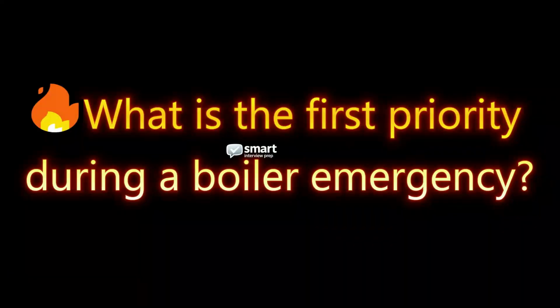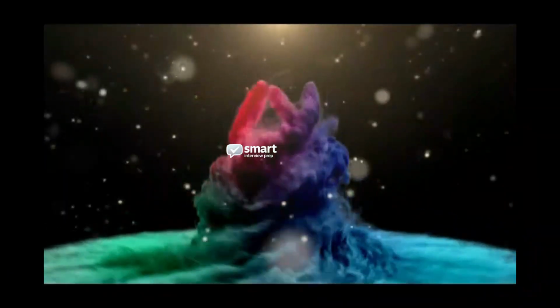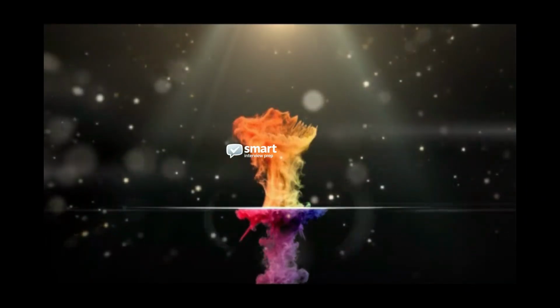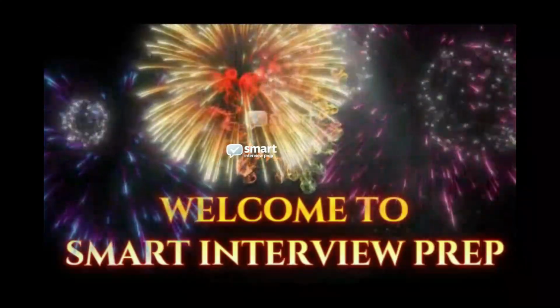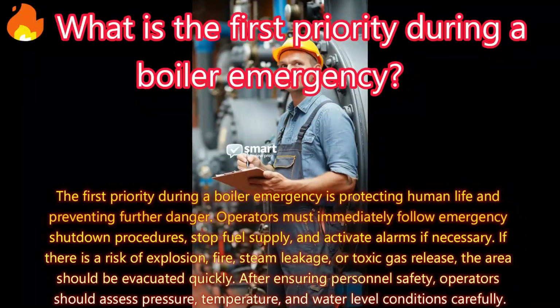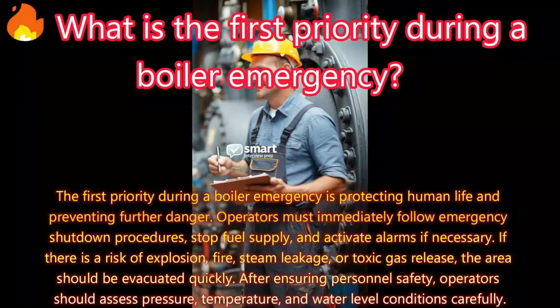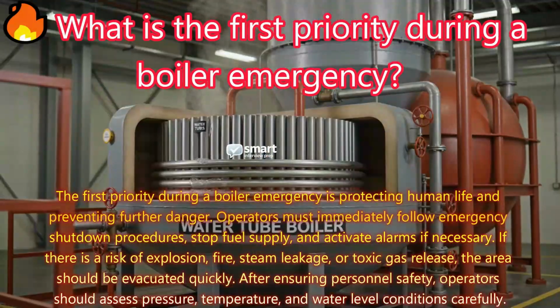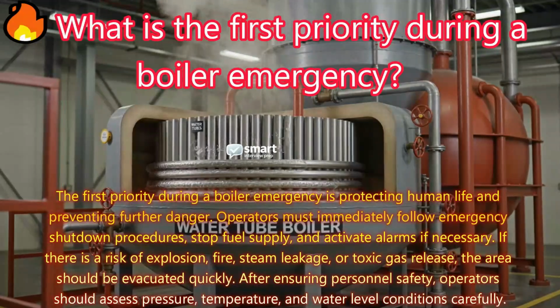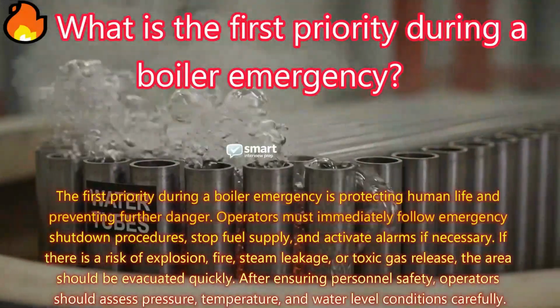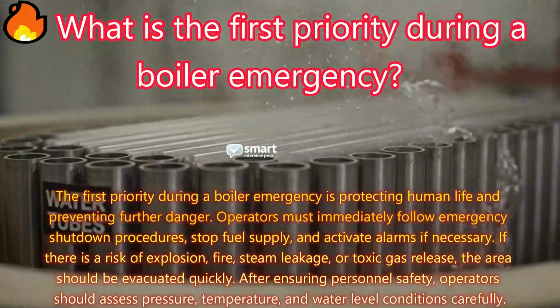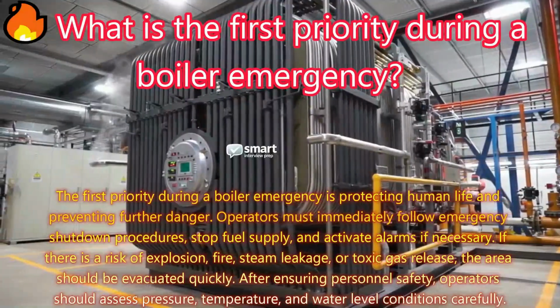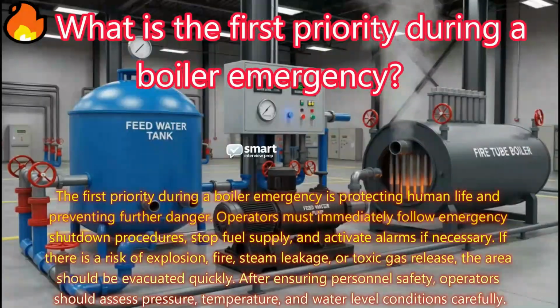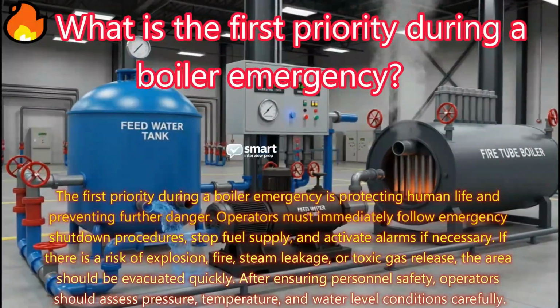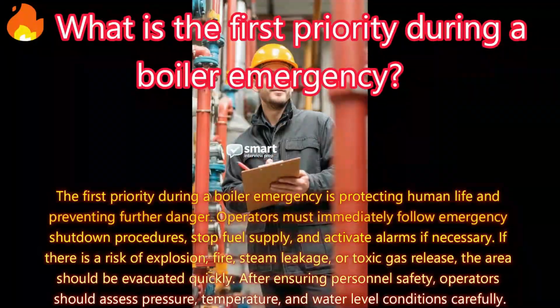What is the first priority during a boiler emergency? Answer: the first priority during a boiler emergency is protecting human life and preventing further danger. Operators must immediately follow emergency shutdown, stop fuel supply, and activate alarms if necessary. If there is a risk of explosion, fire, steam leakage, or toxic gas release, the area should be evacuated quickly.